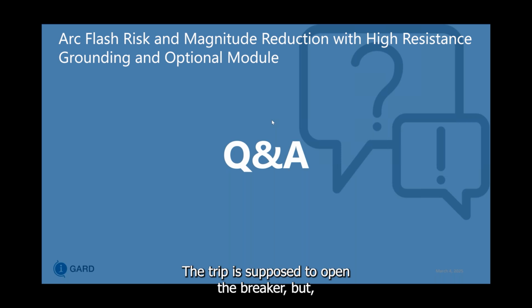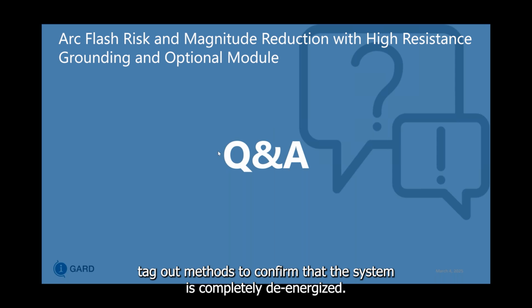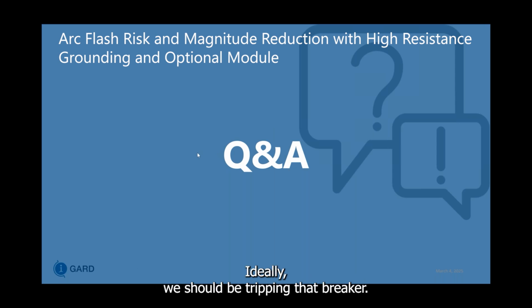Would the trip lock out the breaker? The trip is supposed to open the breaker, but you would have to further verify with lockout tagout methods to confirm that the system is completely de-energized. Ideally, we should be tripping that breaker, so it should be in the open state.